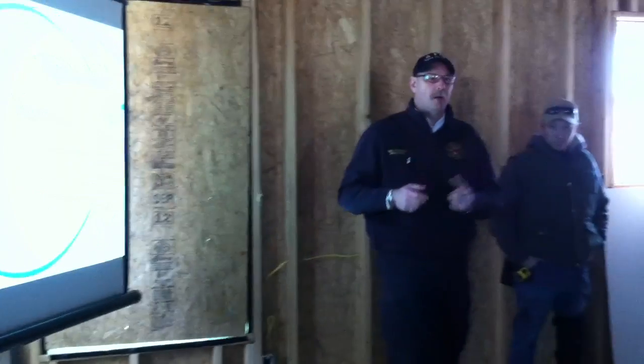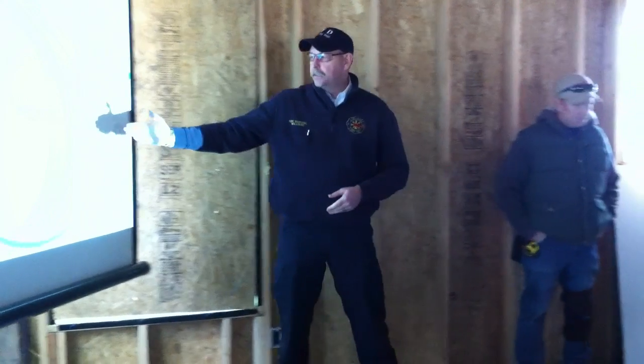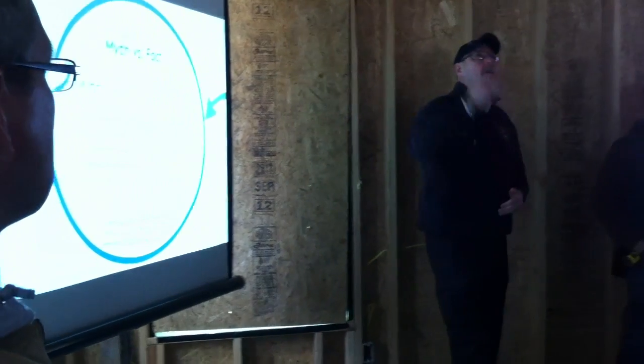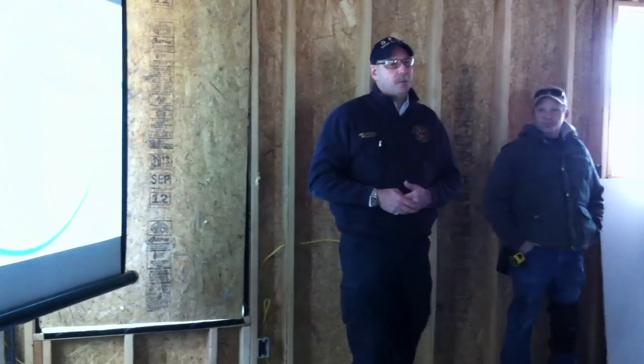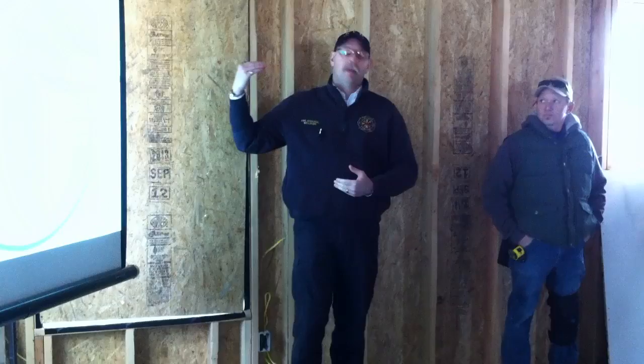False activation: there are a lot of misnomers about it. People think if they burn some toast, the sprinkler head will go off and flood the whole house. That's not true. It's only based on the heat temperature sensor of that head, and these heads are rated at 165 degrees.